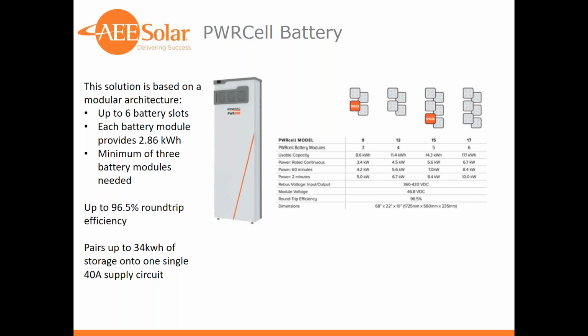One thing that's great that often gets undersold in discussions around modularity and upgrade paths is you're giving yourself a reason to follow up on customers in the future. You're laying out those Hansel and Gretel breadcrumbs to say, hey, we did this project last summer. Sounds like the system's running great. We're checking it out on our portal. All signs go, but you may need more power. It looks like you're cycling this every 1.3 days. With a little bit more power, we can give you more autonomy for that next shutdown. You're building in an upgrade path and a reason to turn a customer into a returning and recurring customer.